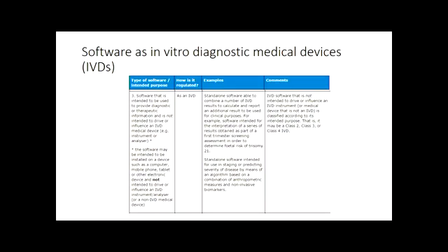And when it comes to IVD, there is a distinction. Software that is used to just run the instrument or analyzer is not a medical device, but if it's used to interpret the data that the instrument collects, then it is. And the IVD classification system applies as well.